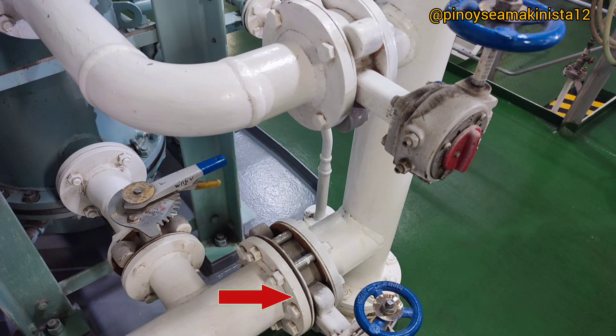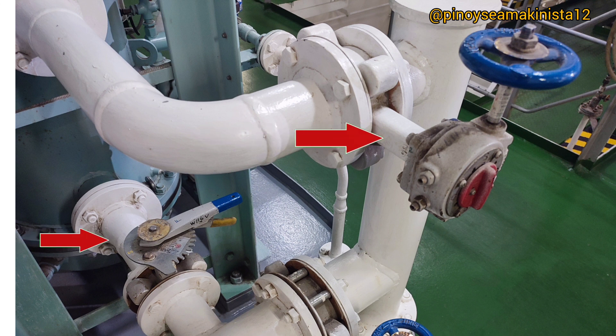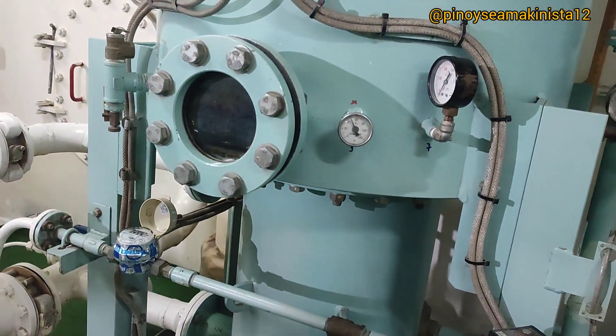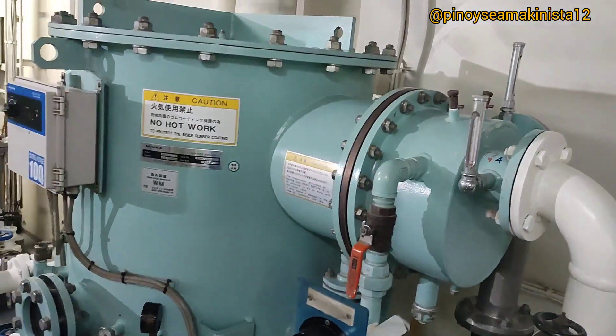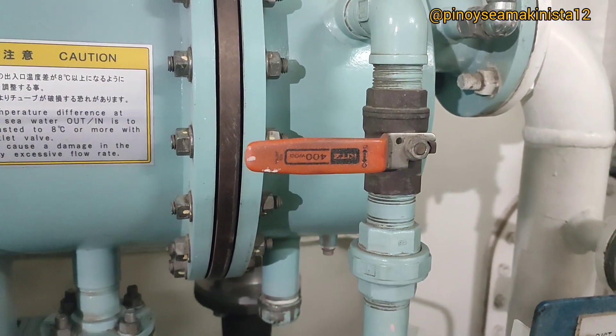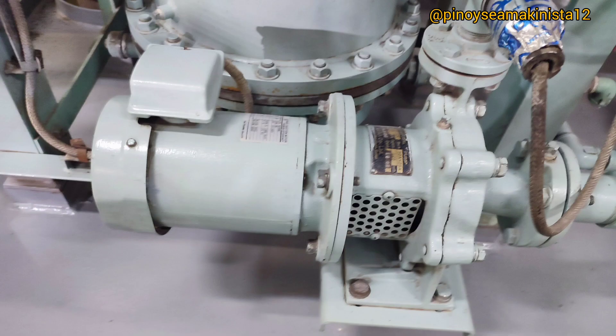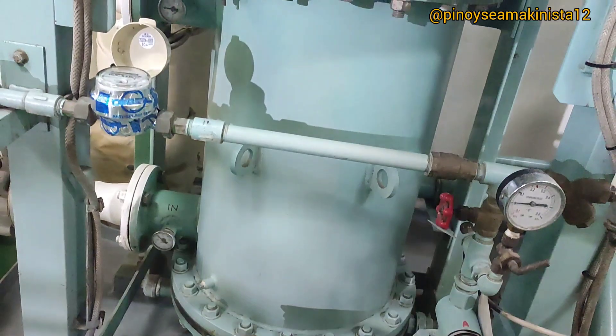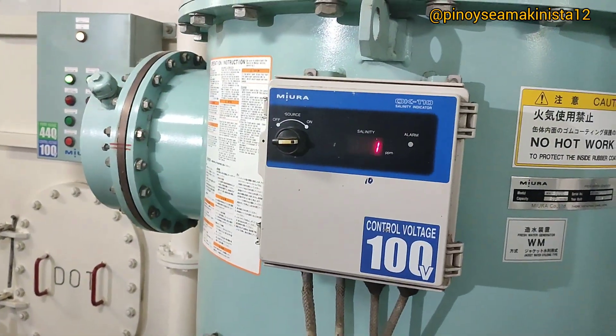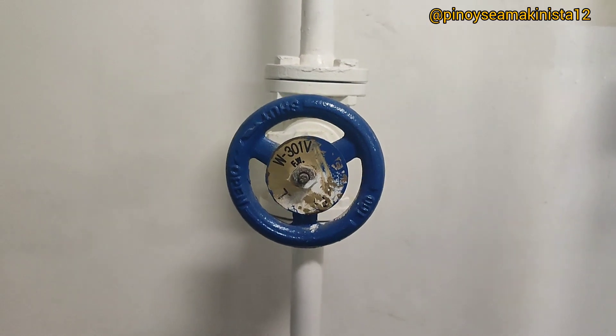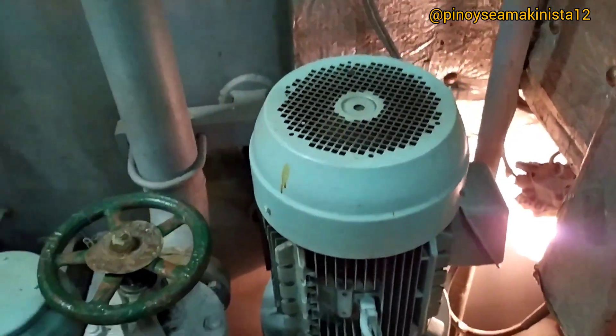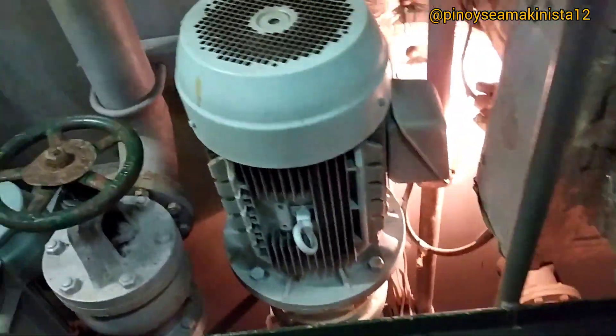How to stop the fresh water generator: Fully open the main engine jacket cooling bypass valve and fully close the inlet and outlet valves of the main engine jacket cooling. Confirm that boiling has stopped from the sight glass of the evaporator shell. Close the feed water valve and chemical dosing valve. Stop the distillate pump and close the discharge valve. Switch off the salinity meter box and close the filling valve to the fresh water tank.